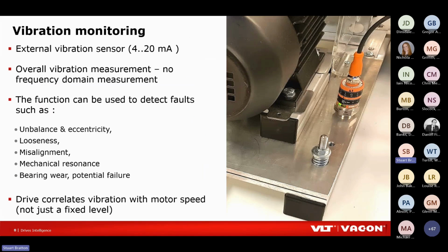If we think about vibration monitoring specifically, we're not monitoring in the frequency domain. We're measuring, let's say, an RMS vibration, and we're correlating that against any particular motor speed. So the sorts of things that we're going to detect are unbalanced loads or eccentricity or looseness or misalignment of shafts, depending on the type of sensor that we use, whether it be a velocity or an accelerometer type sensor. It's possible to also detect higher frequency vibrations that are indicative of potential bearing failure.